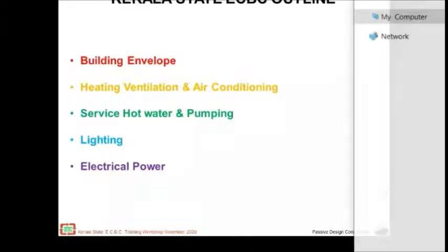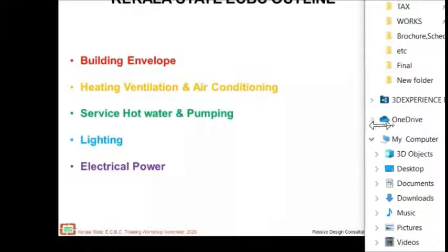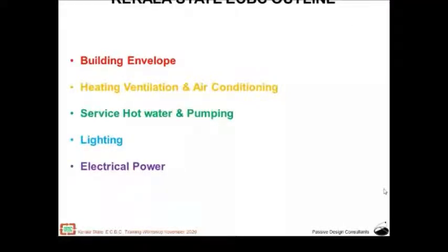And then from there on, within the project, how is the electrical power distributed: cable sizing, losses in the power cables, and the electrical motors that we use in the project for different purposes, like air conditioning systems or domestic water pumping, STP water pumping, etc. Different kinds of motors that we install in the project. What should be the minimum efficiencies of these equipments?